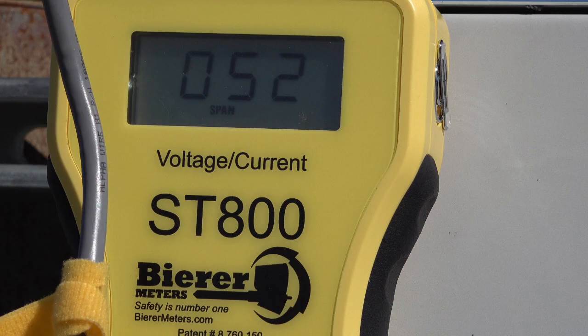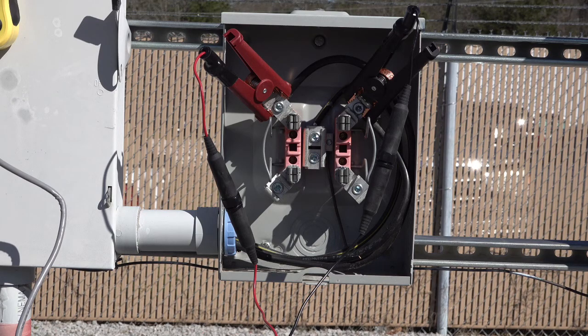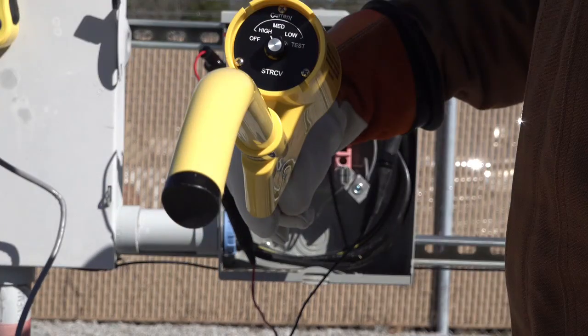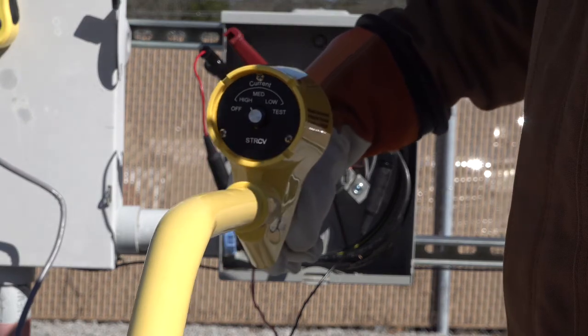If the hot conductors are larger than the neutral, then you should expect to see a higher current reading between both hot conductors. In the same meter base, I've moved the black lead over to the other hot conductor to better demonstrate how the STRCV can identify each conductor. With the ST800 pulsing 800 amps, we want to take our STRCV and put it in the high position. This is for 300 amps and greater. The medium switch position will be used for anything between 50 and 300 amps, and the low switch position will be used for anything less than 50 amps.